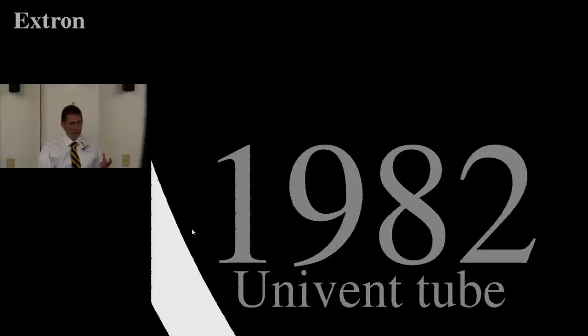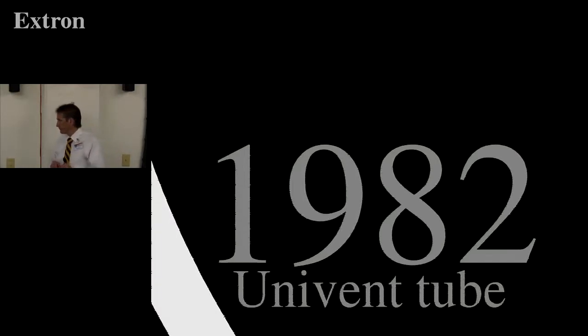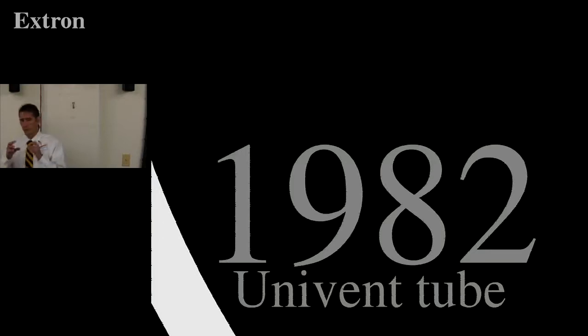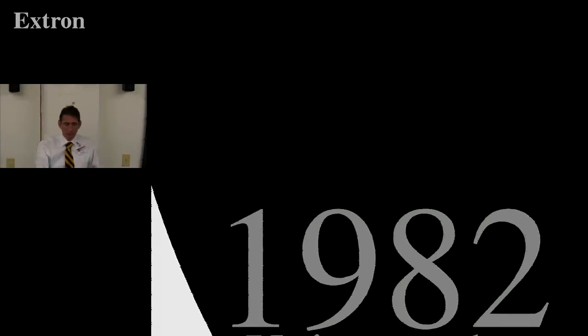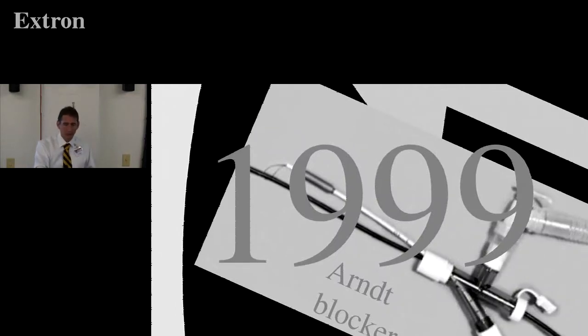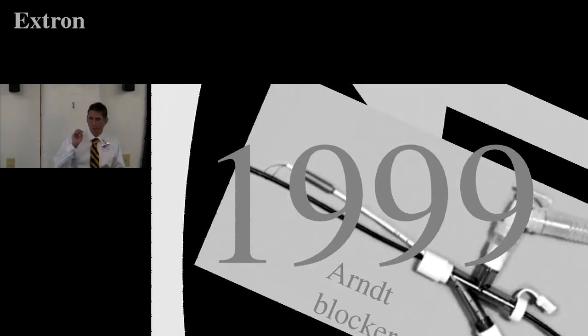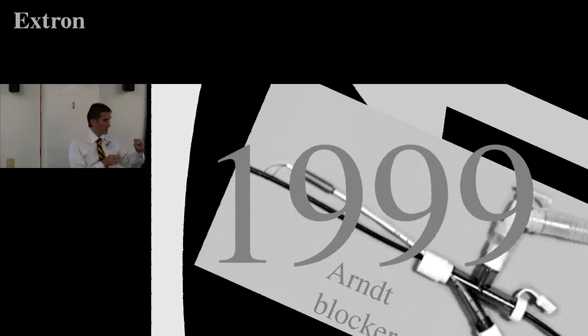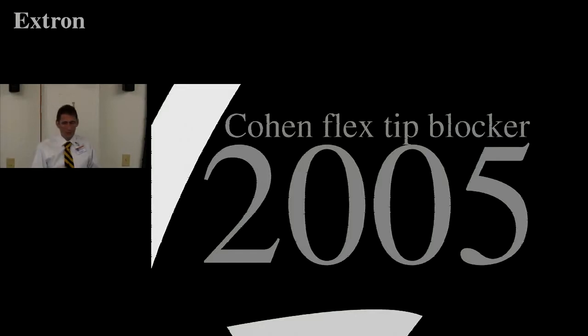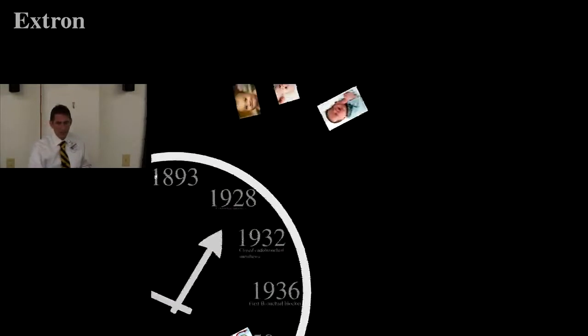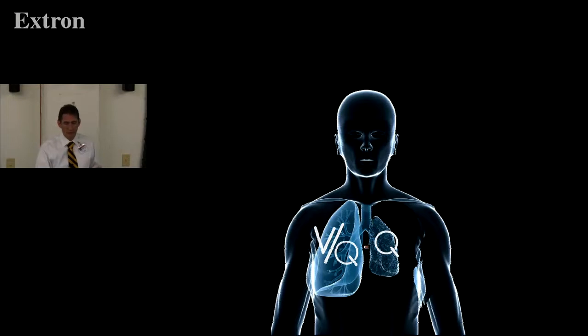People were using Fogarty catheters in the 80s. Then in 1982 Inouye and colleagues introduced the Univent tube — the first single tube with a bronchial blocker incorporated into it. The Arndt bronchial blocker is a fiber-optic-guided blocker: you put the fiber optic down the bronchus you want, the blocker is looped around it, then slide it off the end of your fiber optic scope into the correct bronchus. There's also the steerable Cohen blocker introduced in 2005.